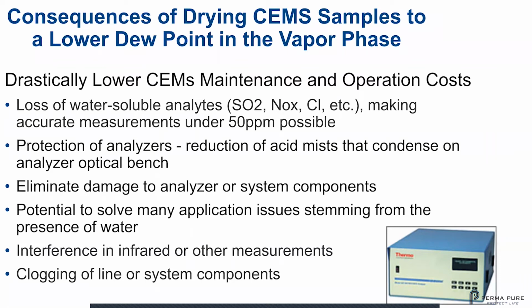And that means a couple of things, and we do that in the vapor phase. So the loss of water-soluble analytes, SO2, NOx, we don't lose those analytes. So we could make accurate measurements under 50 parts per million. Many of the new areas in the world are requiring very low rates of SO2, whether it's a marine CEMS or in other countries such as China. Like we have a lot of experience in Southern California and other places that are deciding to limit their emissions. The only way you're going to really make accurate measurements is by using a Nafion tubing dryer in your SEM system.